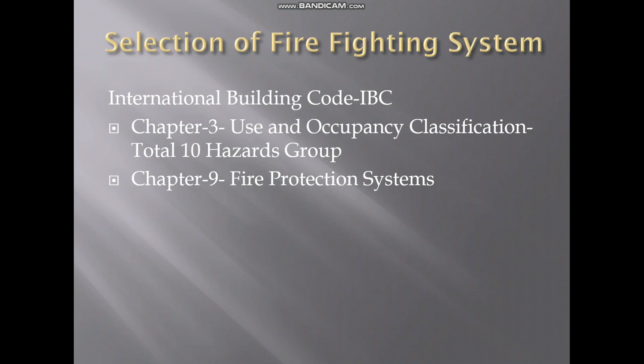We normally use international building codes or local civil defense regulations to decide the firefighting system. If you go to International Building Code chapter 3, it defines the different occupancies, and chapter 9 defines the firefighting requirement for each occupancy, like whether we need a sprinkler, standby, standpipe system, extinguisher, or any other system.